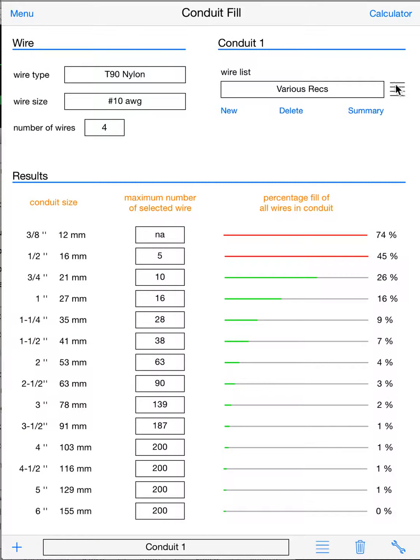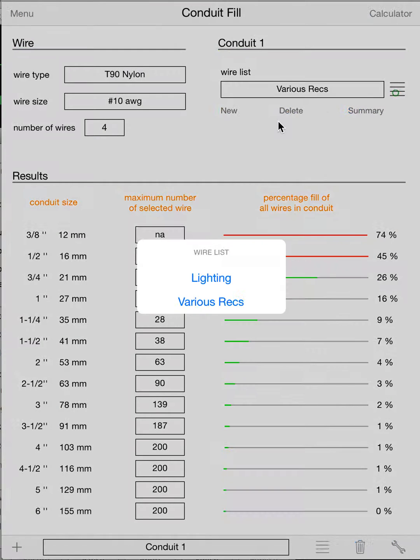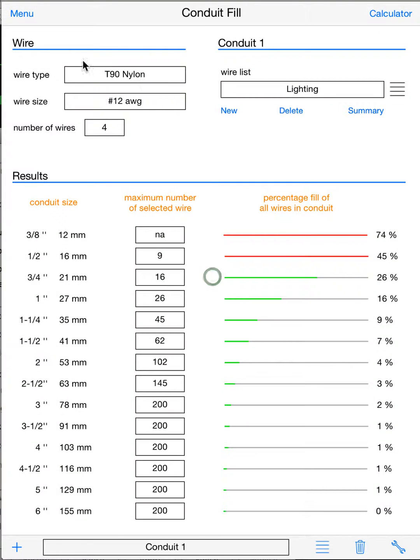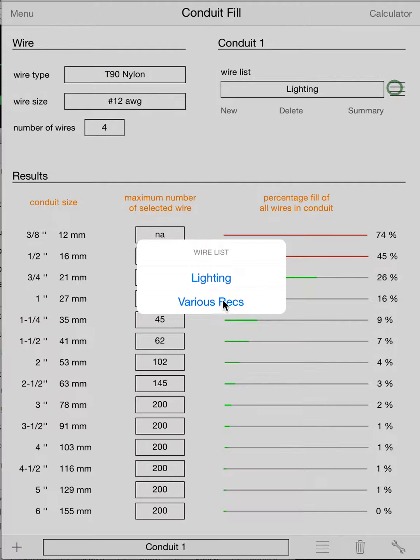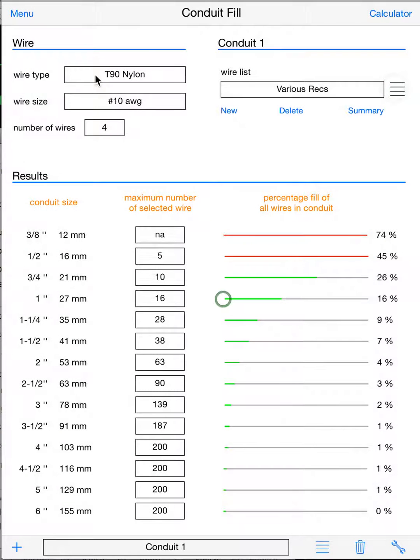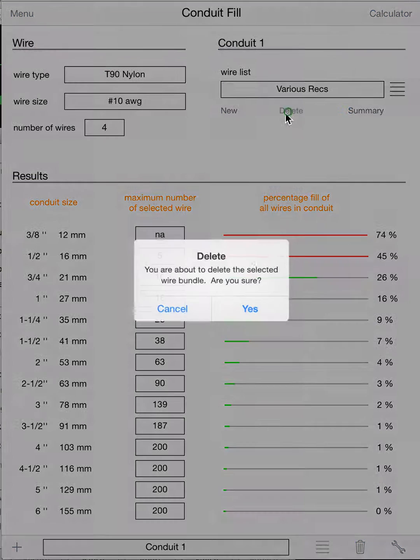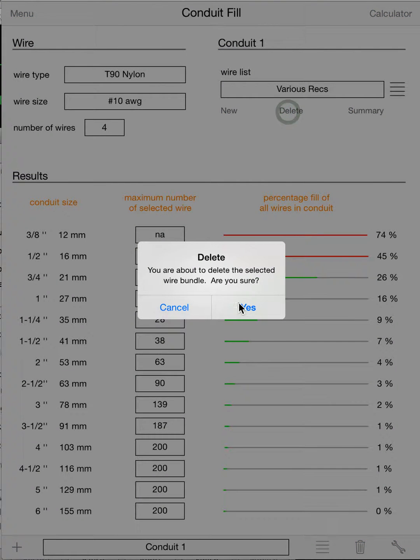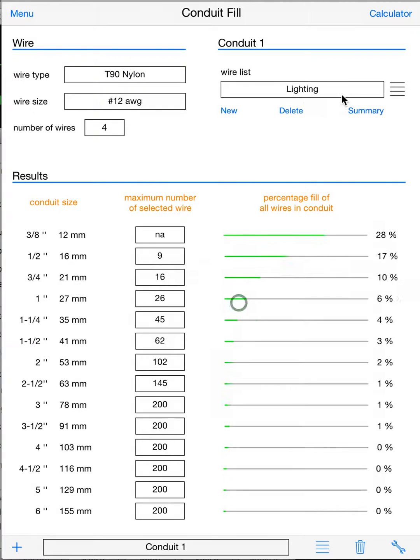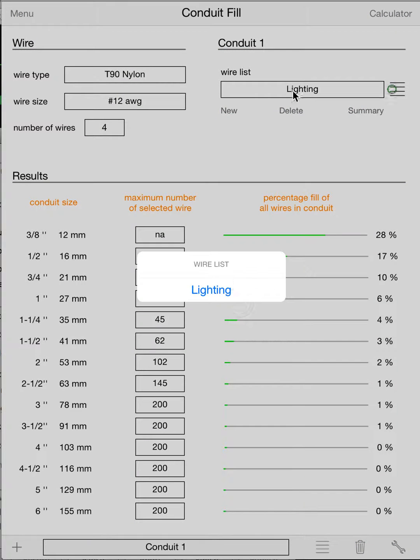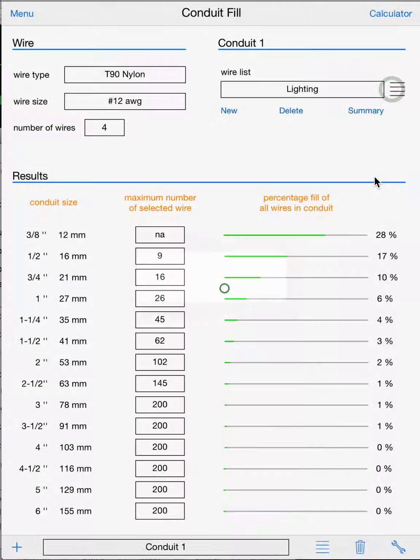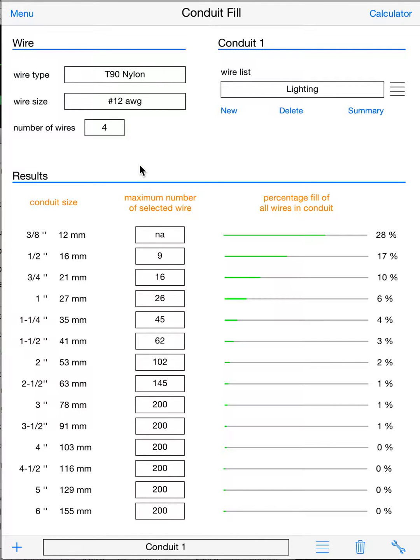And of course, you can select bundles. When you select a bundle, it will come up in the wire area. Of course, you'll see that's our number 12s and that's our number 10s. You can edit them at this point. You can also delete a selected one. So let's say we don't want our various recs. We hit delete. Yes. That one's gone. We're back to a single bundle, and now we can fit in half inch. Three-eighths is NA right now because the Canadian code book doesn't list an area for three-eighths. If you go to NEC, that will become relevant.